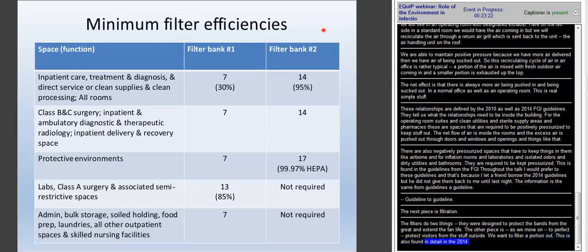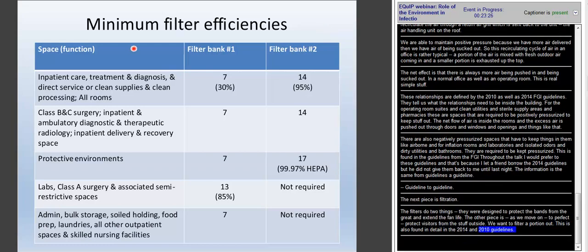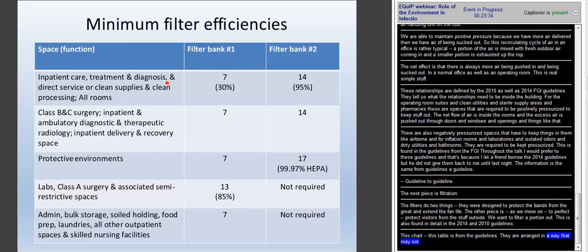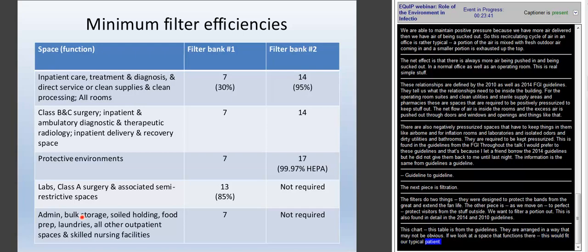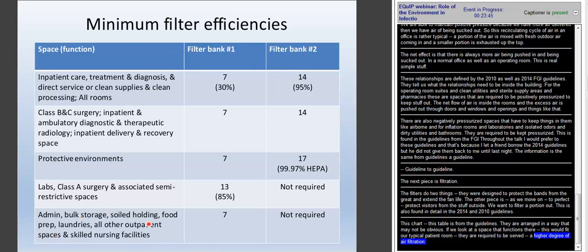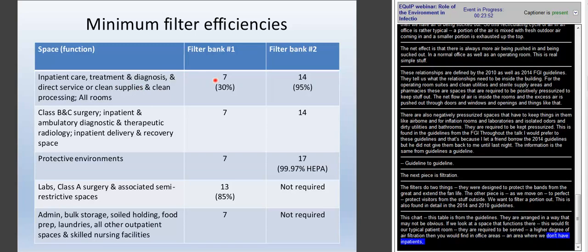So this table here is from those guidelines. And they're arranged in ways that may not necessarily be obvious. If we look at a space and by what functions are there, our typical patient rooms are required to be served and get a higher degree of air filtration than you would find in an office area, an area where we don't have inpatients, for example. So for each space, it'll detail what kind of filters you need to have in which filter bank.